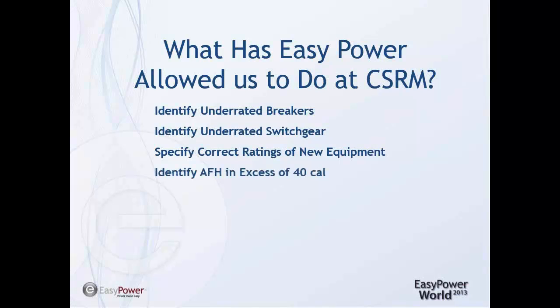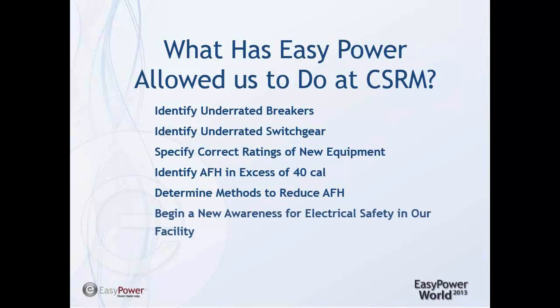We've identified areas where we're in excess of 40 cal, and we have procedures to deal with that. We can determine alternative methods to reduce arc flash hazard. The maintenance button on the relays is just one of the methods we're using.